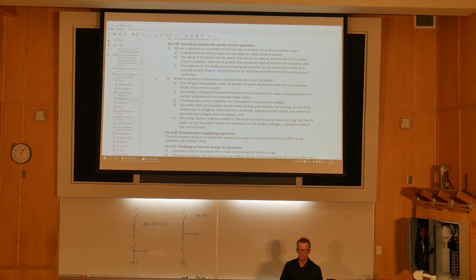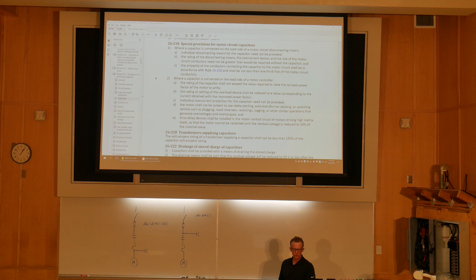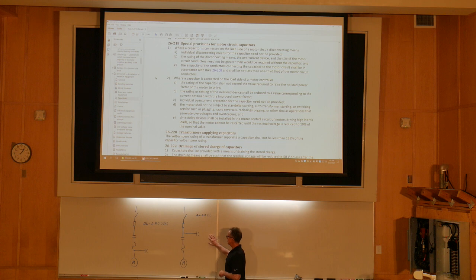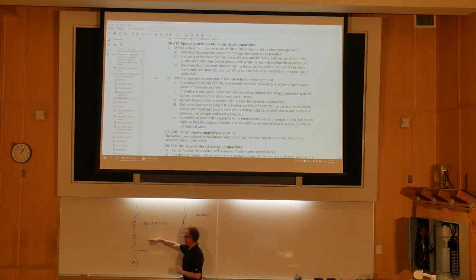All right, so now we're going to look at 26218, special provisions for motor circuit capacitors. So here I've got two pictures. We can do power factor correction right on the motor branch circuit, and there's two spots where to hook up the capacitor. On the load side of the disconnecting means here, and this is also on the load side of the disconnecting means, but the difference is, in this one it's on the load side of the motor controller. It's on the load side of the overloads. That's the key here. And here, it's on the line side of the overloads.